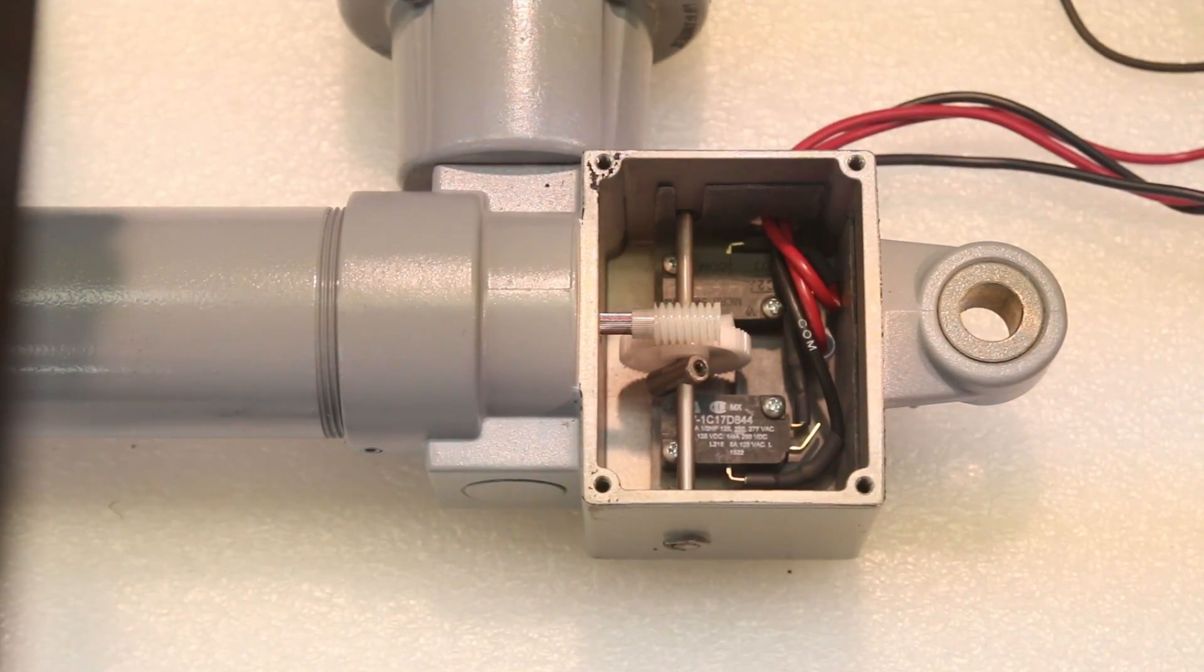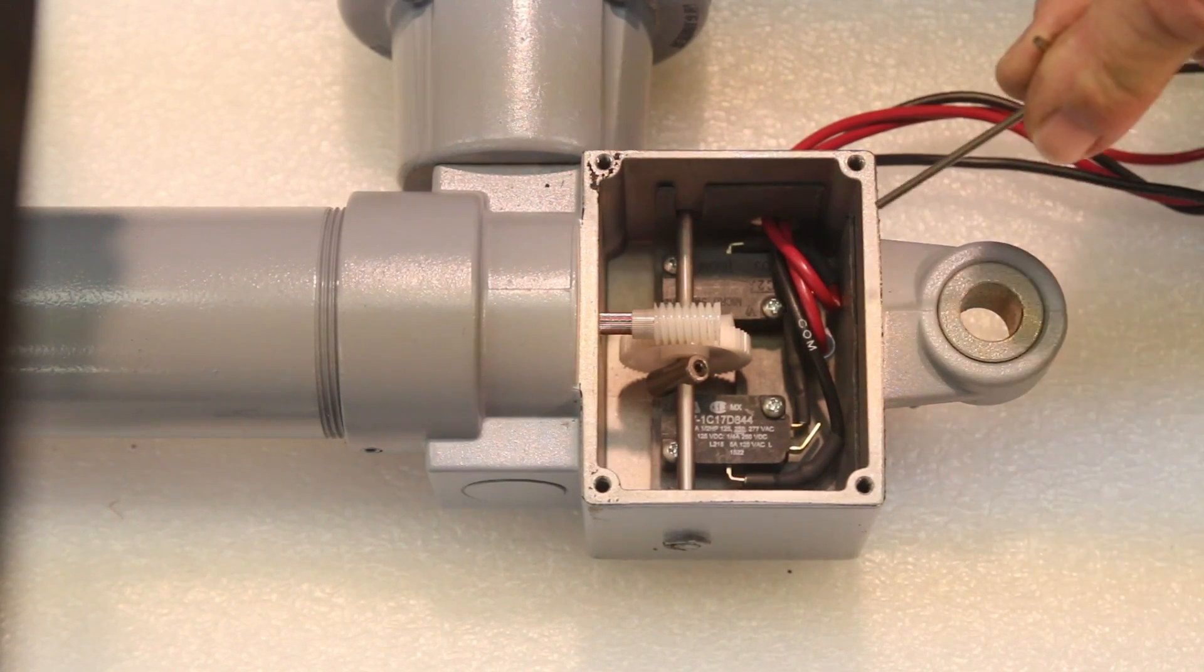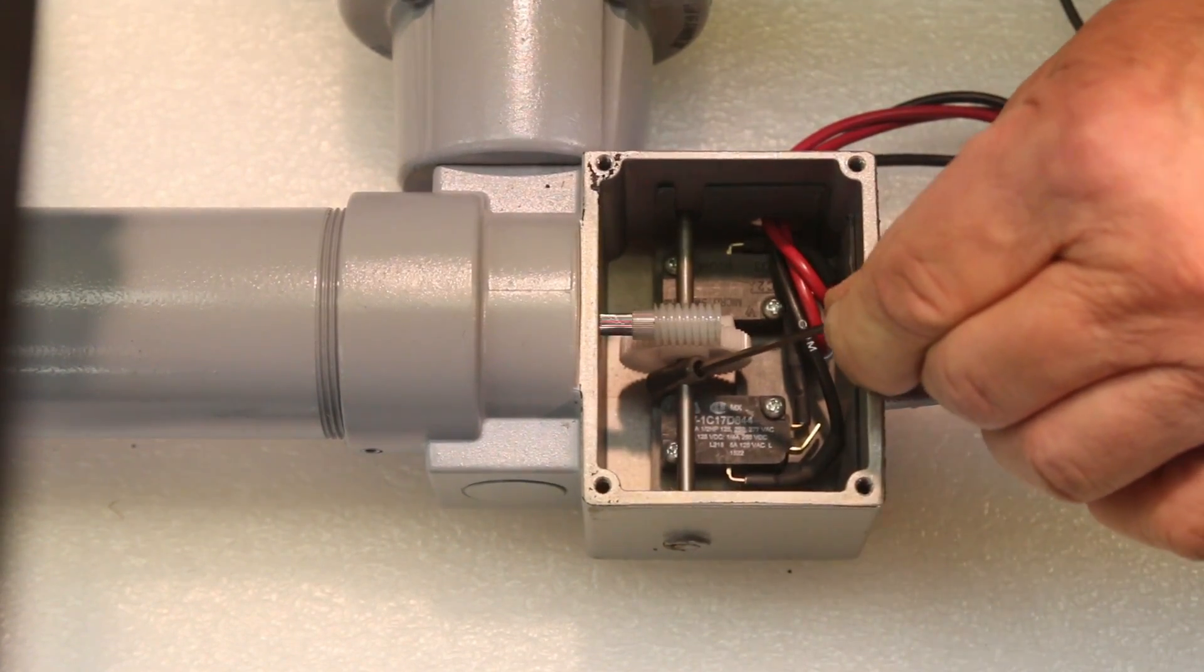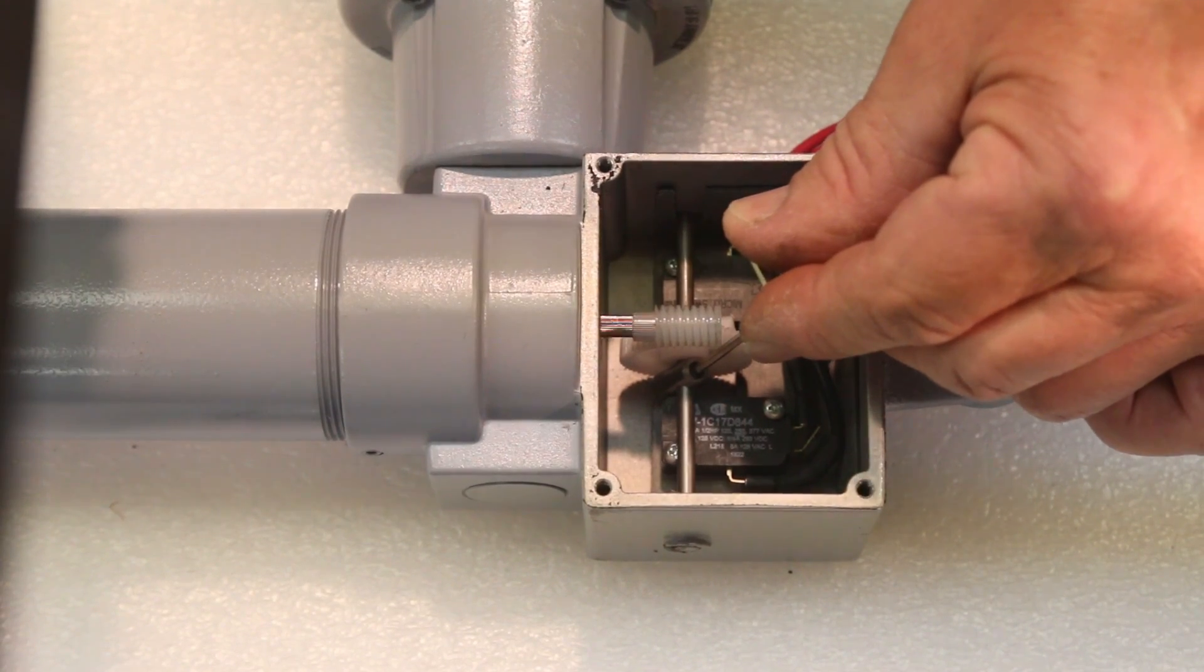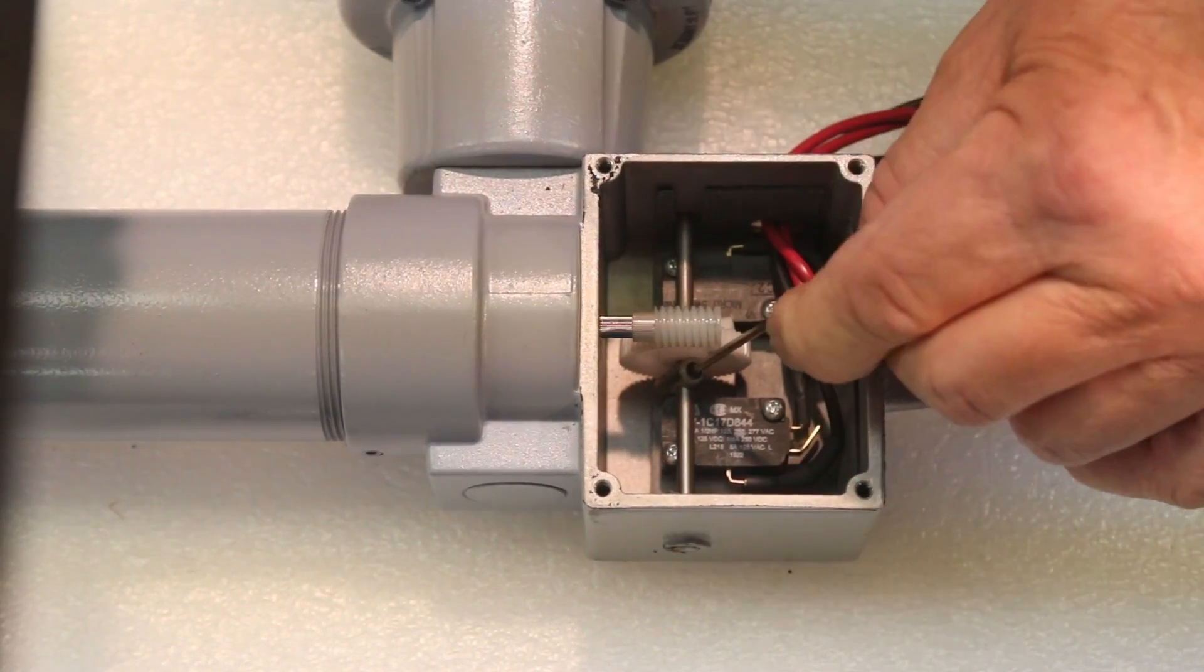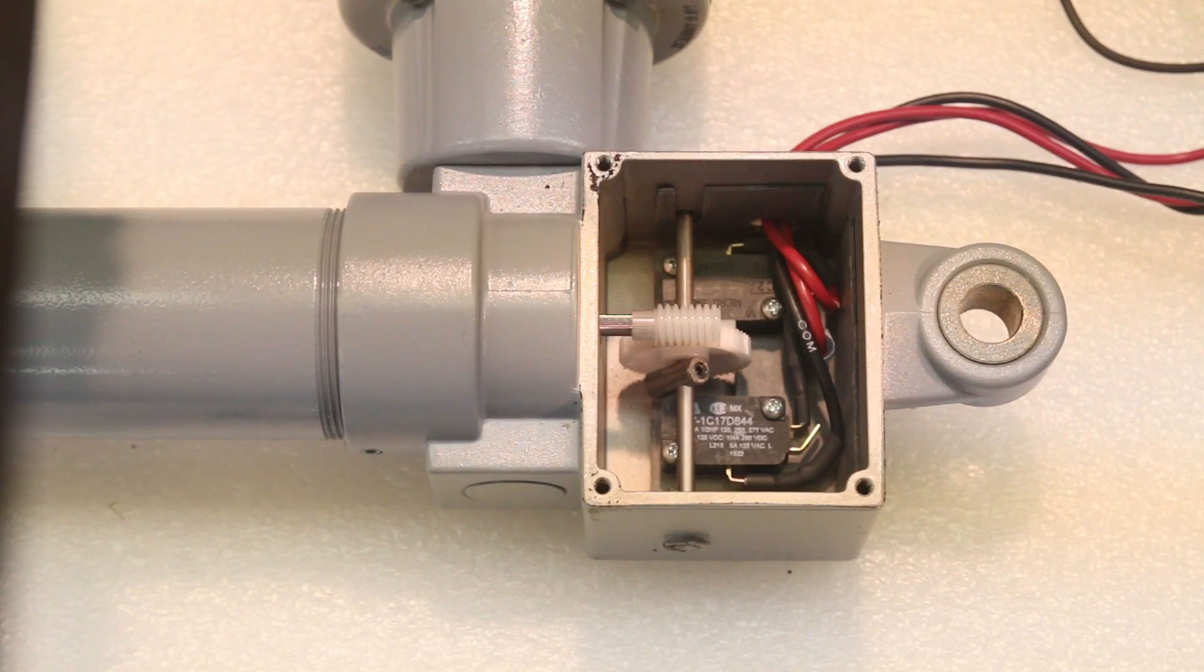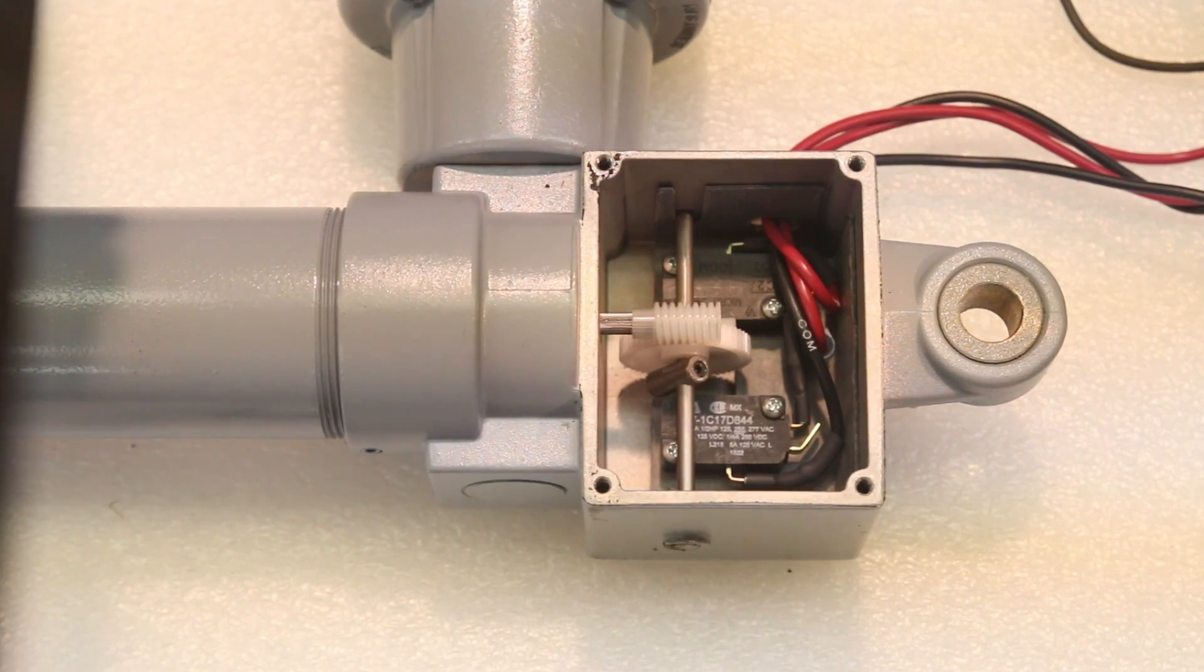Once we have achieved the extended height, we will adjust the steel adjustable cam until we actuate the extend limit switch. This is done by using the allen wrench for a lever. We hit the switch, and we tighten the set screw. This then prevents the actuator from running in the extend direction. It will run in the retract direction, and then back to the extend direction until the switch is actuated.